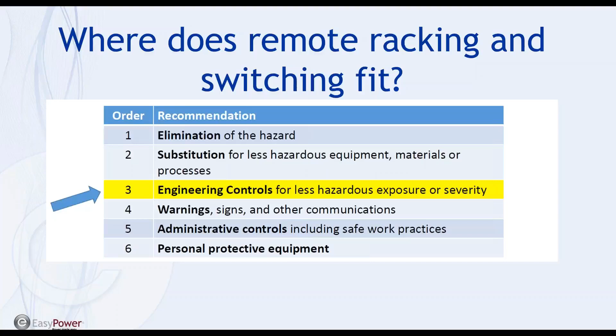So I'm going to back that statement up for a second and say that I think it's better to take a systems approach to this. And by that, I would say that you need to have administrative controls in place by upper management and supervisors that say that, if remote switching and remote racking is available, we're mandating that it is used. And you also need the warning signs and other communications in place, such as the arc flash labels that say, here's what the actual hazard is, and here's how far you need to be away, and set that parameter. And then it depends too on training and making sure that people will utilize the equipment correctly for it to be an effective engineered control. And so even though when used correctly, our devices are certainly engineered controls, they have to be used correctly. You have to follow the warnings, and ideally management is bought into this as a solution and mandates its use whenever applicable.